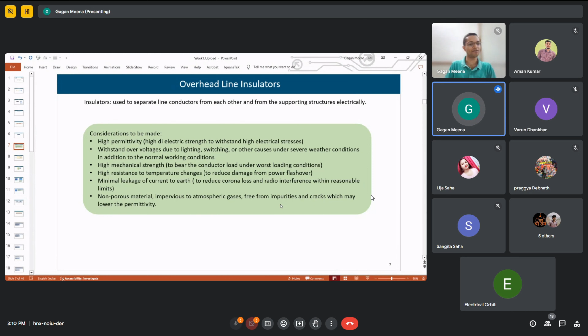Then the next part which was discussed was the electrical failure of insulators. There are two types of failure: one is puncture and another is flashover. In puncture, the electrical arc passes through the body of the insulator, and after that there is permanent damage to the insulator, and we cannot use that insulator further. How can we reduce this? The remedy is to provide sufficient thickness of the material so that we can prevent it.